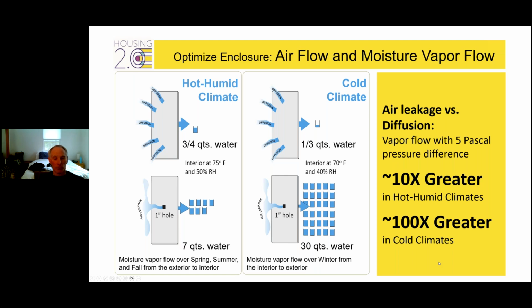The moisture flow over the winter from interior to exterior goes from 1/3 quart up to 30 quarts of water, 100 times greater vapor flow. So this is really simple: air leakage is way, way more important than just managing thermal flow or energy losses through leakages. It's also imperative for moisture control.